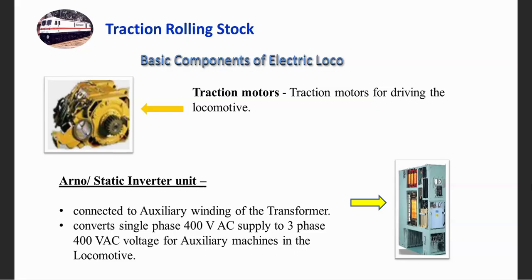In case the Arno converter fails, none of the auxiliary machines can work in the locomotive, and even if the entire power circuit is working, the loco is declared dead. We cannot operate the locomotive if the Arno converter fails to convert single phase AC supply to three-phase AC supply. So the reliability of the Arno converter was very important, and later, as technology developed, we got rid of the Arno converter and replaced it with the static inverter, which is now a microprocessor-based system provided in the locomotive.